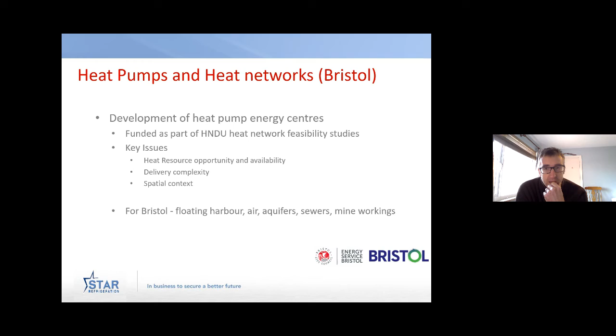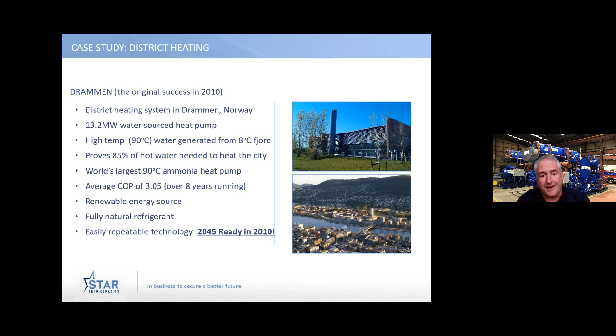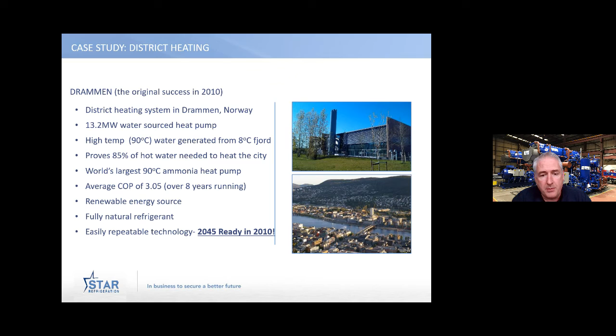So what gives us the confidence to say this? Well, the simple answer is we've done it - 10, 12 years ago now, over in Norway. It's a seawater sourced heat pump, still I believe the largest 90-degree ammonia heat pump operating in the world. We're always advocating lower and lower temperatures - every degree we lower the flow temperature saves about 1.5% of running cost. But that's what was needed there - lots of old buildings, and it's been running for quite some time, so they could claim to be 2045 ready already back in 2010.